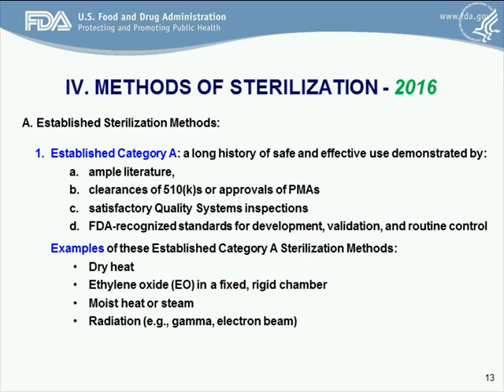Taking a closer look at established category A methods — these are methods that have a long history of safe and effective use, as demonstrated by ample literature, clearances of 510Ks or approvals of PMAs, satisfactory quality system inspections, and FDA recognized consensus standards for development, validation, and routine control. Examples of these include dry heat, ethylene oxide in fixed rigid chambers, moist heat (also known as steam), and radiation — examples include gamma and electron beam radiation.